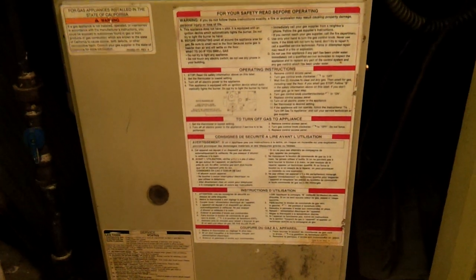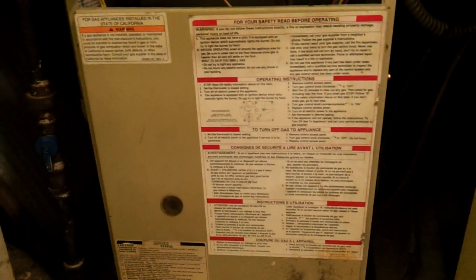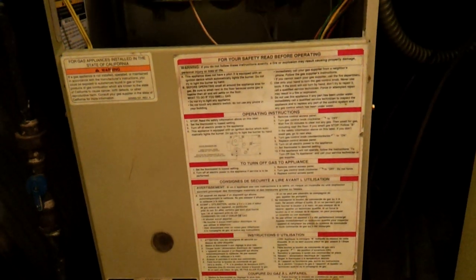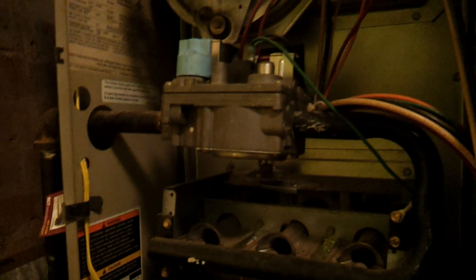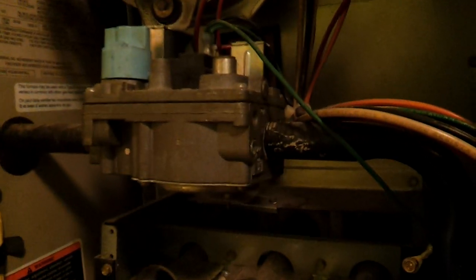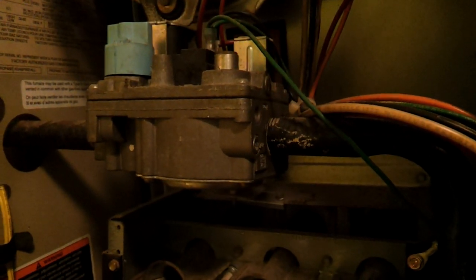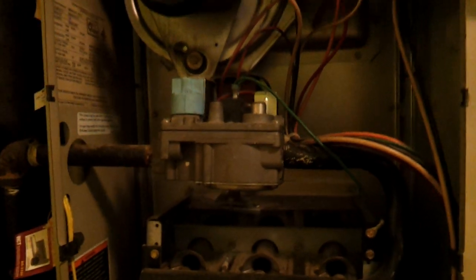3 in-shot burners, which means that they shoot the flames into the heat exchanger, which we'll see here in a little bit. And pretty standard PSC motor blower. It's actually got multiple speeds, which is kind of surprising considering this furnace was made in about 1994, so it's almost 10 years old.